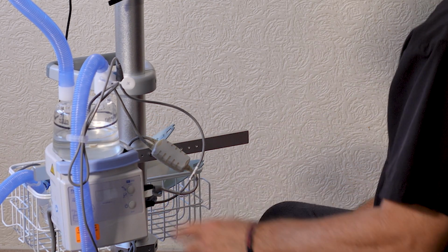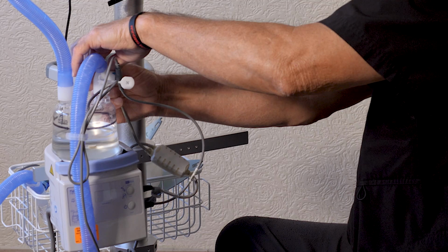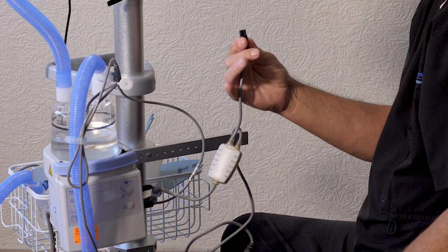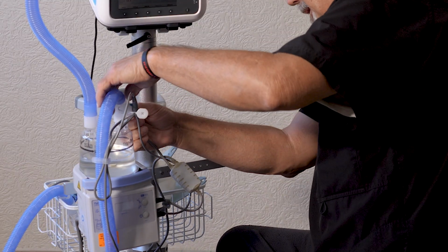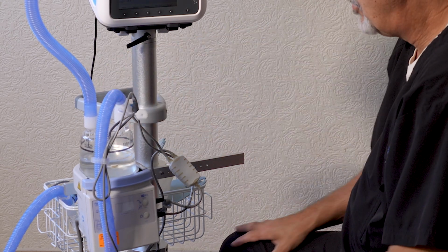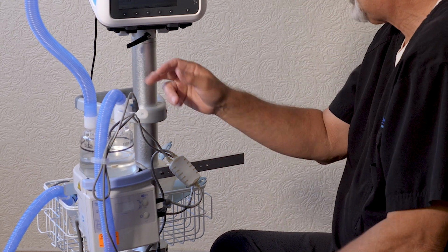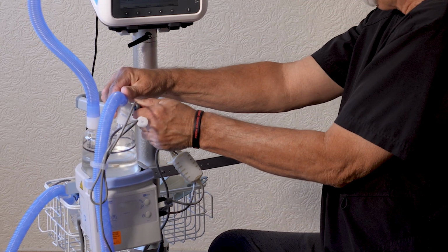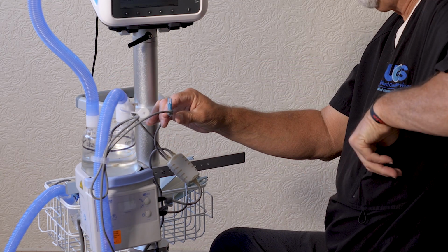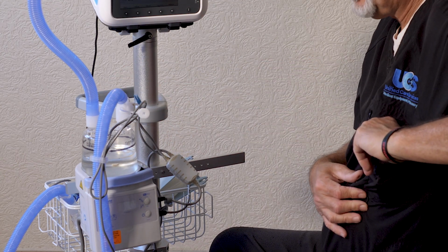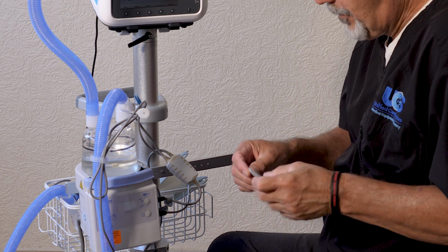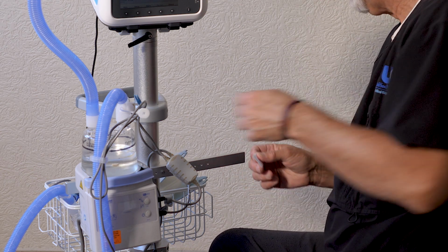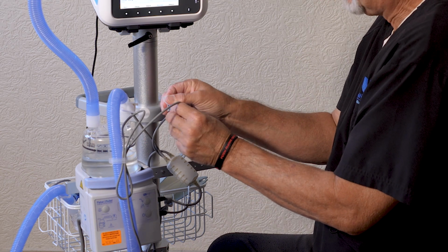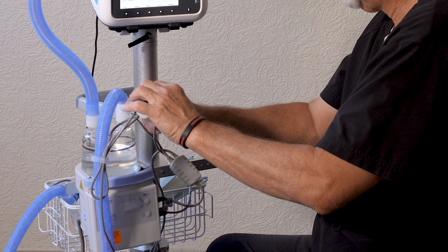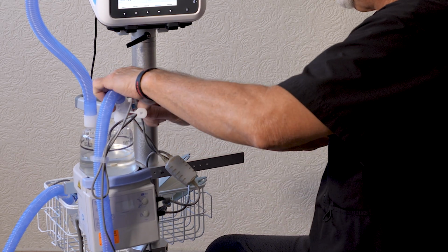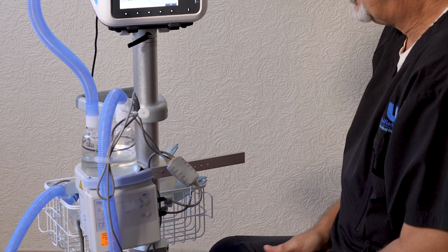And then after you removed and put those two back, you want to come over here and detach the top of the heater wire cable, which has 3 prong things. And you want to line it back up and make sure it goes all the way back in. And then you want to take the temperature probe out. You want to clean it with alcohol, and you do this every single time you remove the temperature probe from the circuit. Clean it with alcohol, carefully align it, and push it back in until it snaps.